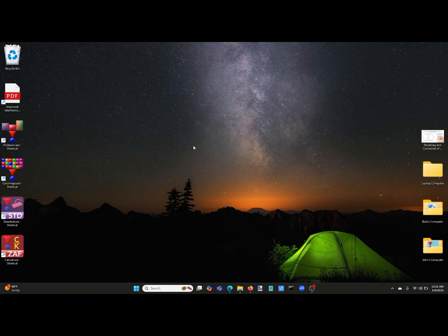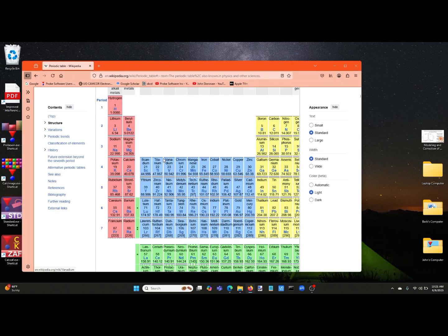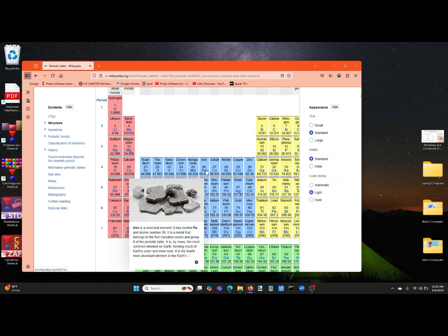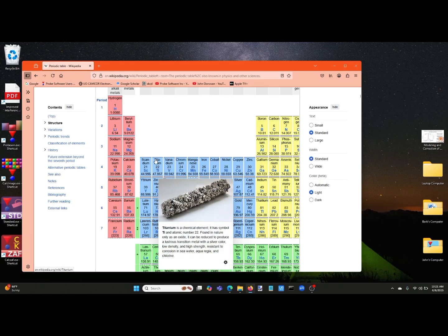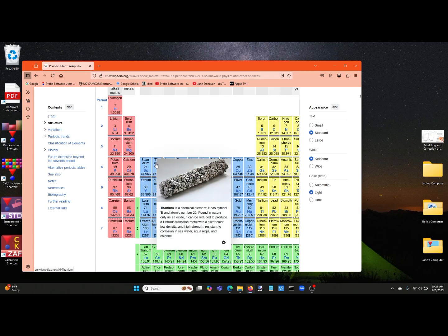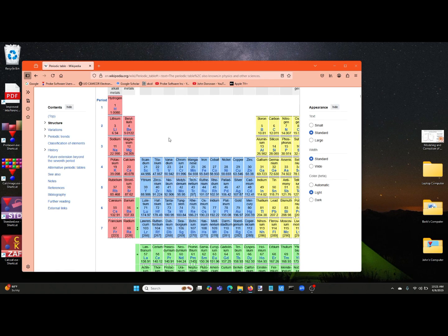Today, we're going to look at the correction of interferences in EPMA, and we're going to start by looking at the periodic table, and we're going to note that there are known interferences and interferences we may not know about. Interferences that we can reliably count on are, for example, the interference when you're measuring trace vanadium in a titanium-bearing mineral. You will get interference of titanium K beta on the vanadium.